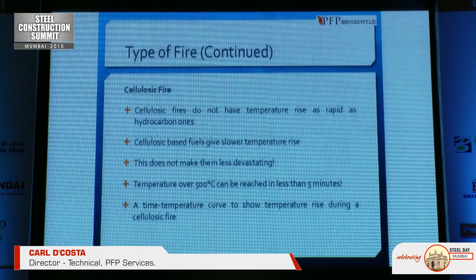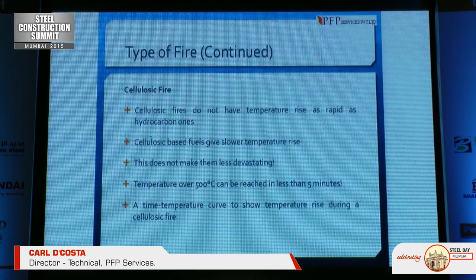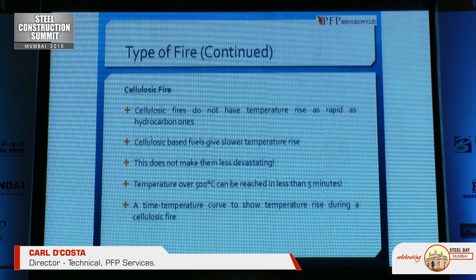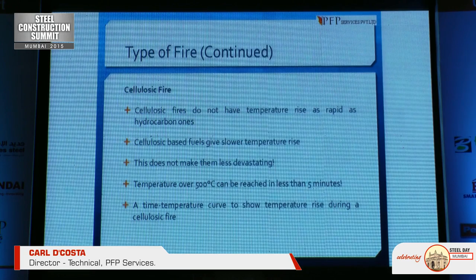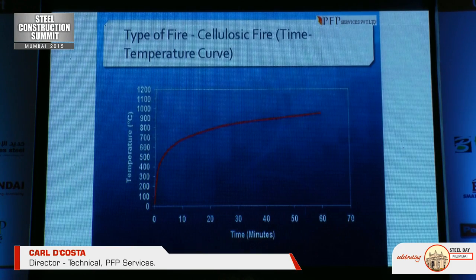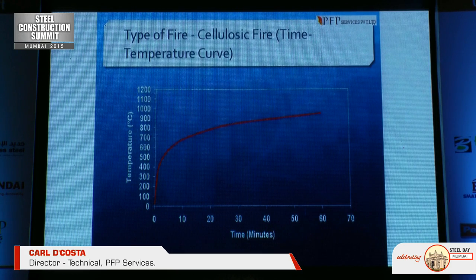Cellulosic fires do not have as rapid a temperature rise as hydrocarbon ones. Cellulosic-based fuels give slower temperature rise, but this does not make them less devastating. A temperature over 500°C can be reached in less than five minutes. The time-temperature curve shows the temperature rise during a cellulosic fire, reaching almost 700°C within less than 10 minutes in a full fire.